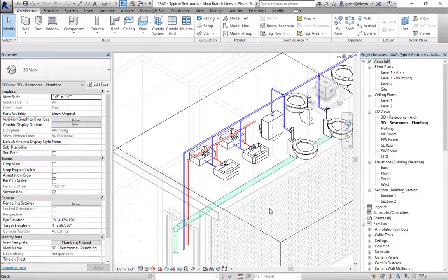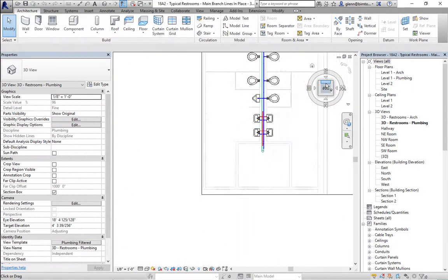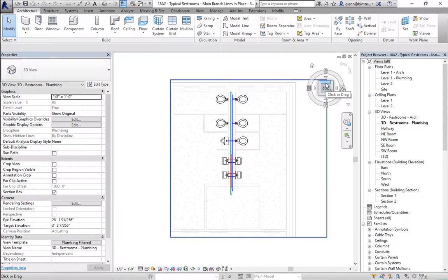The big thing is that cold and hot water pipes are quite okay running at any height or angle — they don't need a slope because they're pressurized. However, the sanitary pipes are the ones you have to be careful about — always make sure you're running downhill from start to finish. The pipes all run into a mechanical room somewhere off on the side of the building. The space needed for pipes to come down is actually quite small. A lot of times they'll be up against the wall, boxed out in the corner by just six or eight inches.